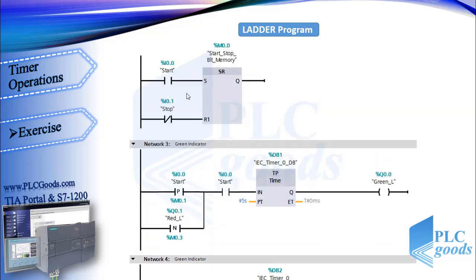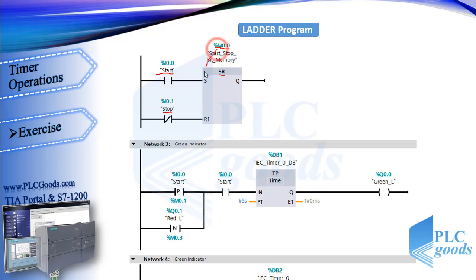Let me use a set reset instruction with start and stop contact as you see. So instead of holding start push button, I can store and hold the start request at a bit memory. Now I use this bit M0.0 instead of these I0.0 addresses.